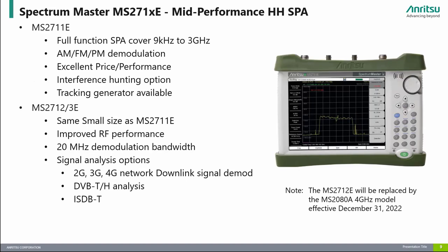The Spectrum Master MS271XE series are Anritsu's mid-performance range of spectrum analyzers. The MS2711E provides frequency coverage from 9 kHz to 3 GHz and offers users great value with its excellent price-to-performance ratio. Note that the MS2711E does not offer digital signal analysis options. Users that need digital signal analysis options should consider the MS2712E and MS2713E, which provide improved RF performance, higher frequency coverage, and various signal analysis options including 2G, 3G, 4G, ISDB-T, and others. The MS2712E offers frequency coverage to 4 GHz and the MS2713E goes to 6 GHz. Please note that the MS2712E will be replaced by the MS2080A 4 GHz model effective December 31, 2022.